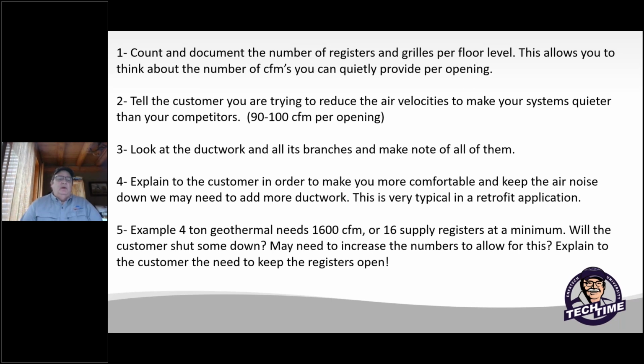Explain this to your customer. Why am I doing this? I want to make you a quiet and comfortable system. So I go look into a house or a home, and let's say I'm going to put a 4-ton geothermal in. So at 400 CFM per ton, I'm looking at 1,600. So I would typically divide by 100, and that gives me like I need 16 supply registers, and that's a minimum. So now, does your customer shut down some during the winter or the summer months? Maybe I don't want to cool the basement or heat the basement or whatever. You guys have to realize that's a mistake and a problem as well. We can't shut down that much airflow, or we need to add a lot more ducts.